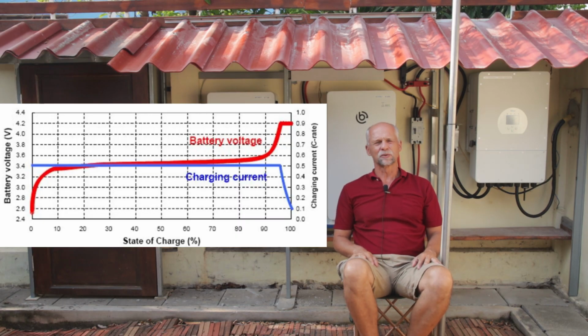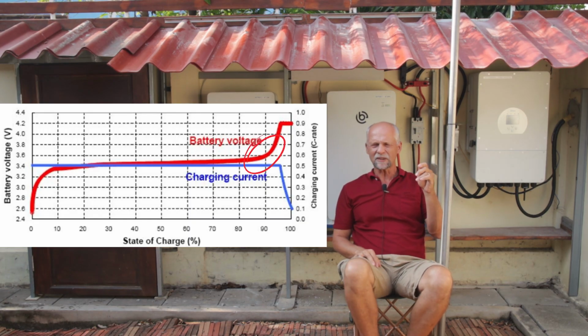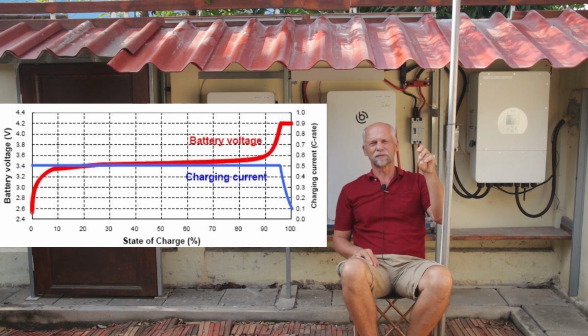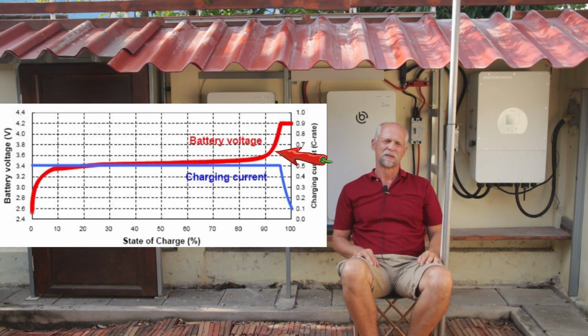So when do we want to balance, or when can we balance? Balancing is actually only done at the top of the voltage curve — we are top balancing. We need to wait until we come out of the flat area, and then when it goes into the final part of charging, when voltages rise rather quickly, we can activate our balancers and they can do their job.